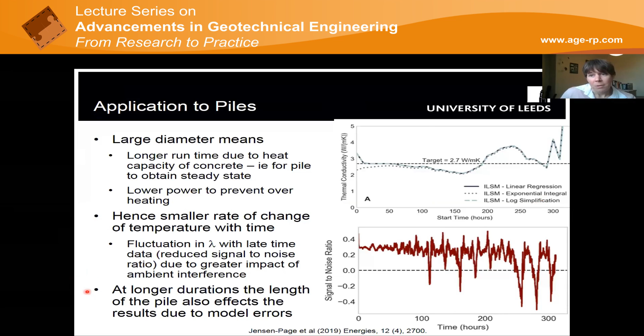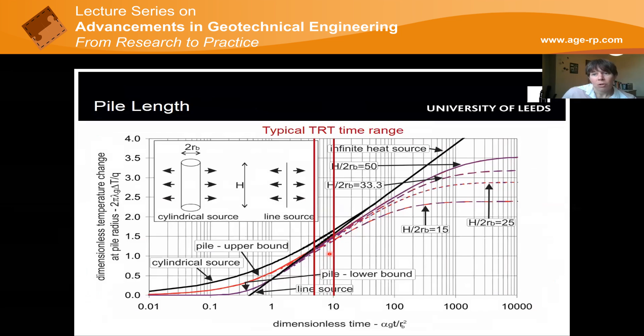This is because we get ambient interference with the ground surface, with the air temperatures, and we get a decrease in the signal to noise ratio with time. The other thing that happens when we run tests for a long time to overcome the pile heat capacity is there are model errors. So I showed this chart before. Between these red lines is the typical time of a thermal response test, and we're fitting this straight line model to it here, but actually our results are probably one of these curves underneath that are kind of purple colored. So you can see we're fitting a curve at the wrong gradient basically, so we get model errors.